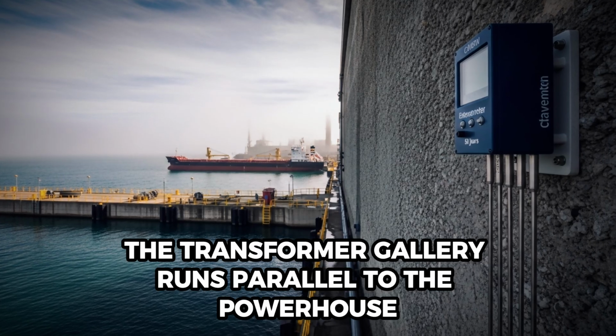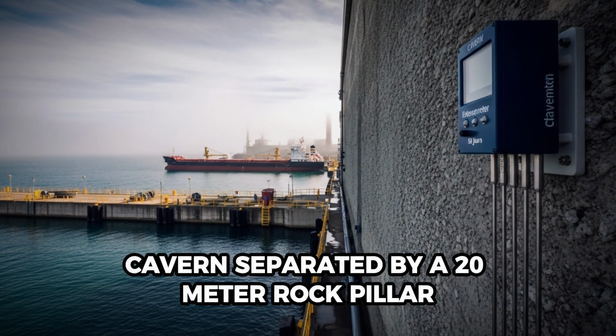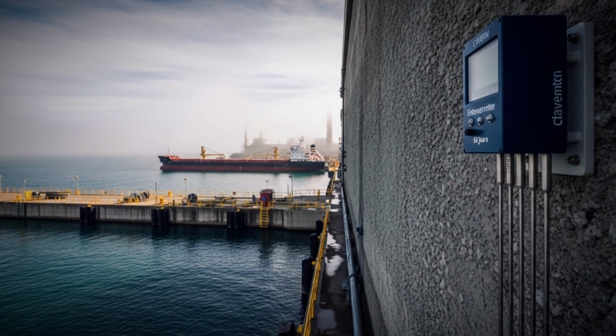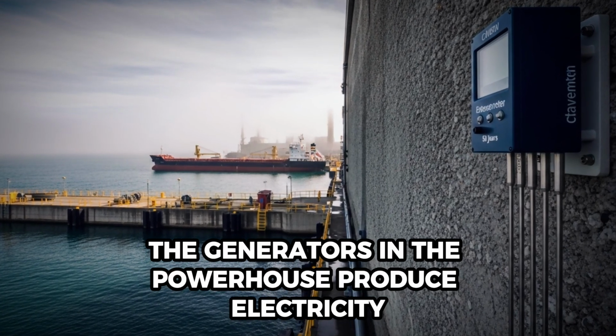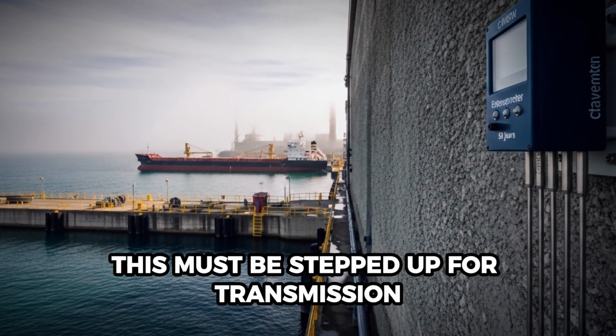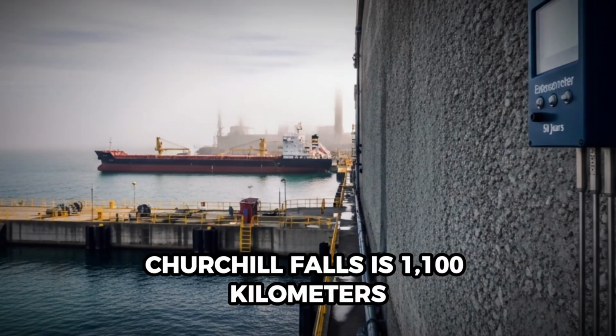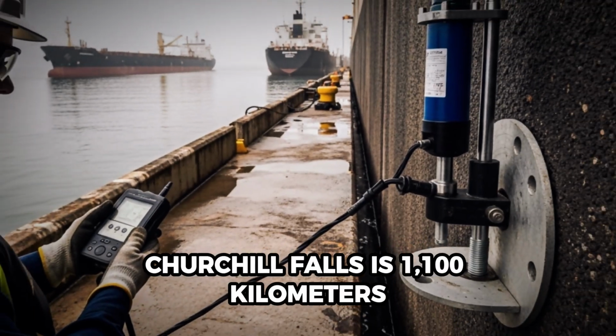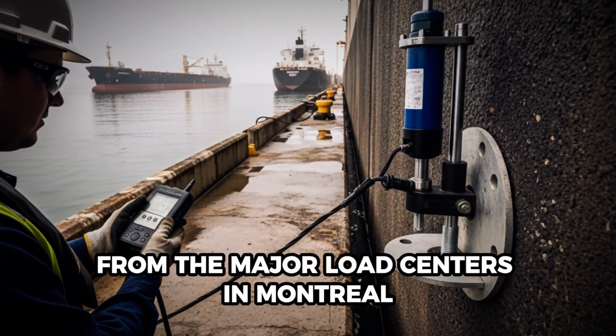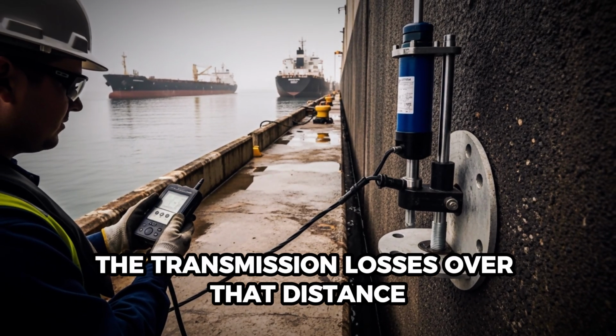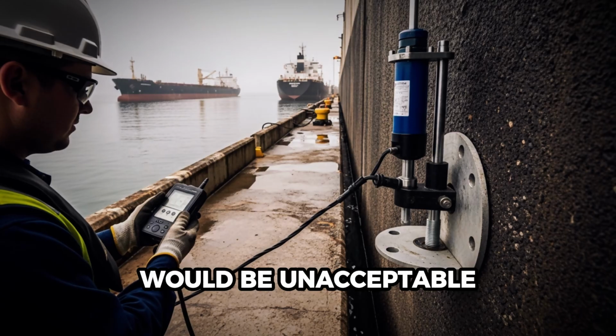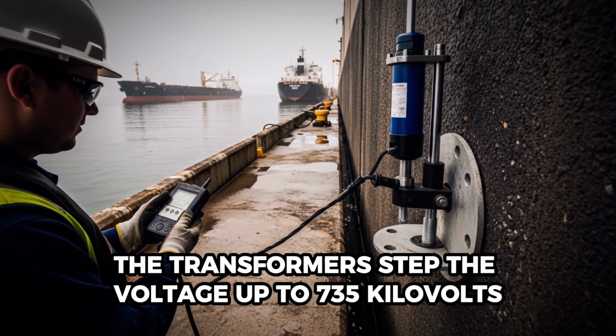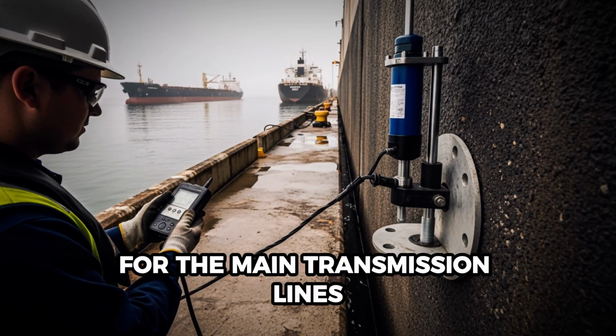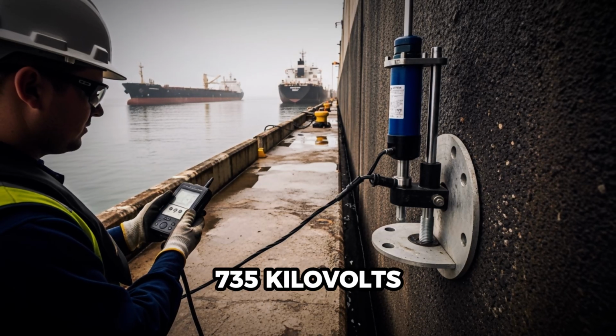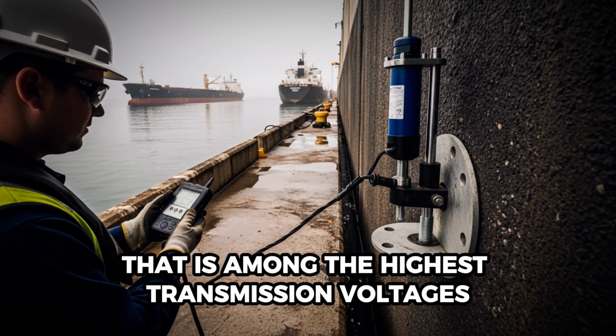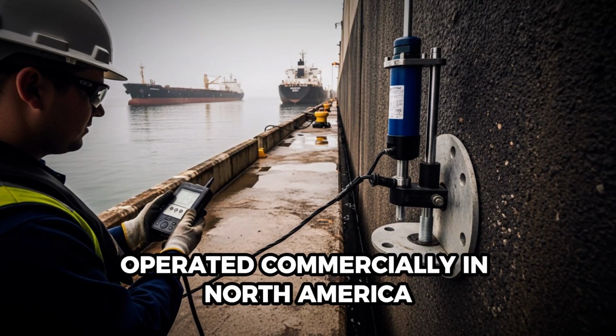The transformer gallery runs parallel to the powerhouse cavern, separated by a 20-meter rock pillar. The generators in the powerhouse produce electricity at 15 kilovolts. This must be stepped up for transmission. Churchill Falls is 1,100 kilometers from the major load centers in Montreal. At 15 kilovolts, the transmission losses over that distance would be unacceptable. The transformers step the voltage up to 735 kilovolts for the main transmission lines. 735 kilovolts. That is among the highest transmission voltages operated commercially in North America.